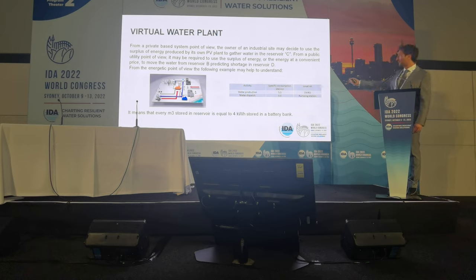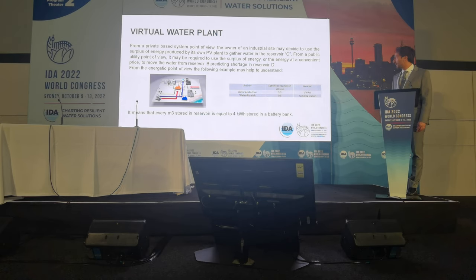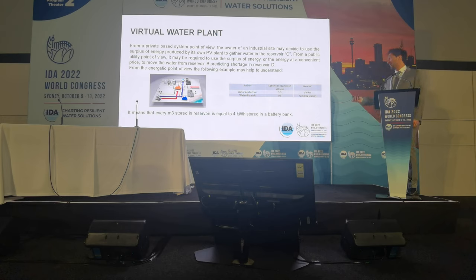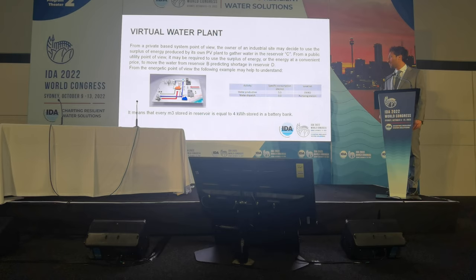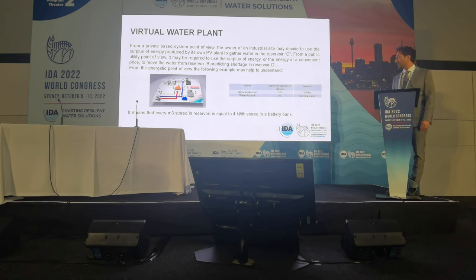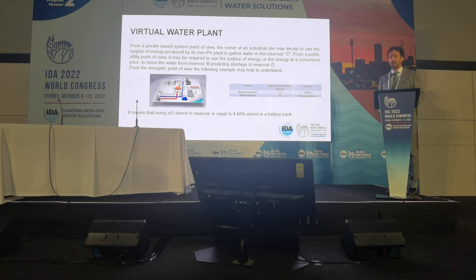For example, producing one cubic meter of water costs 3.5 kWh per cubic meter, while dispatching costs 0.5 kWh per cubic meter. So moving and producing this water is equivalent to storing 4 kWh in a battery, because we will use the water anyway. Why not produce the water when we have the energy instead of waiting until the need arises?